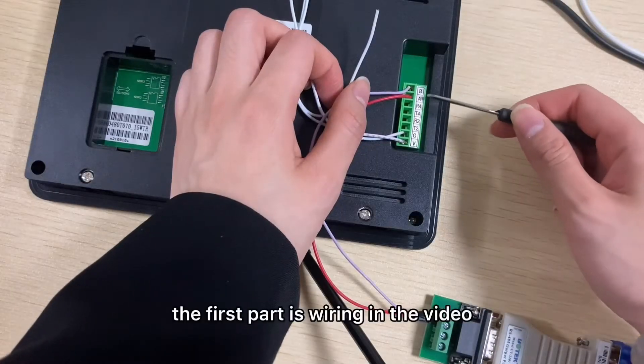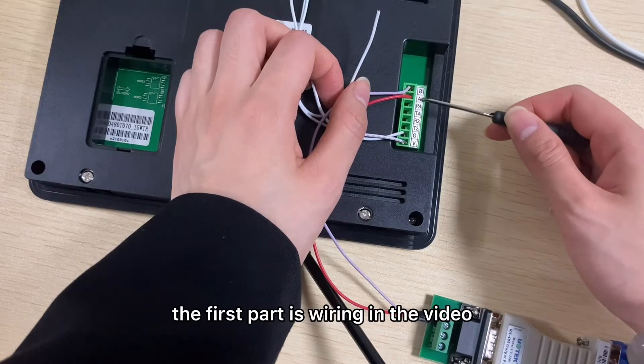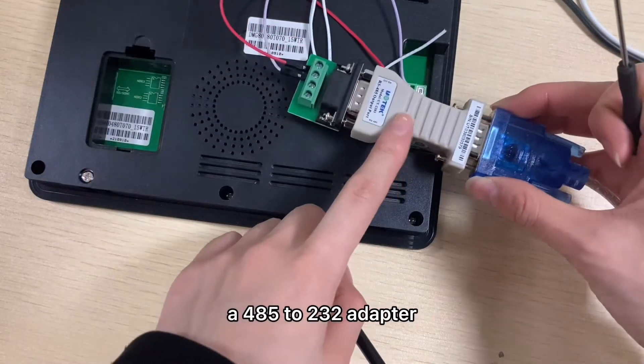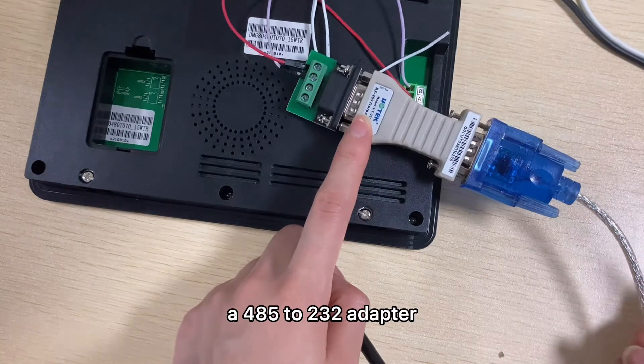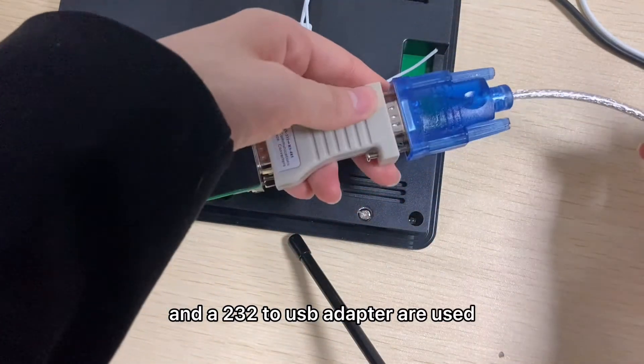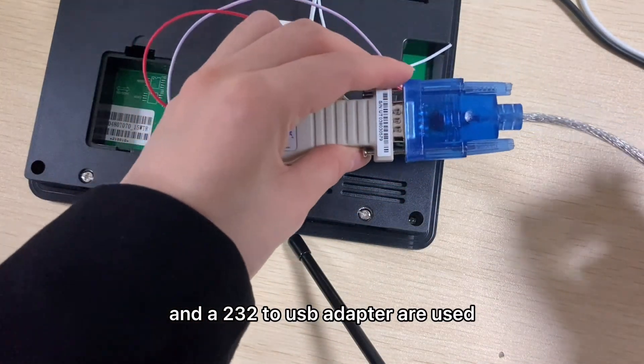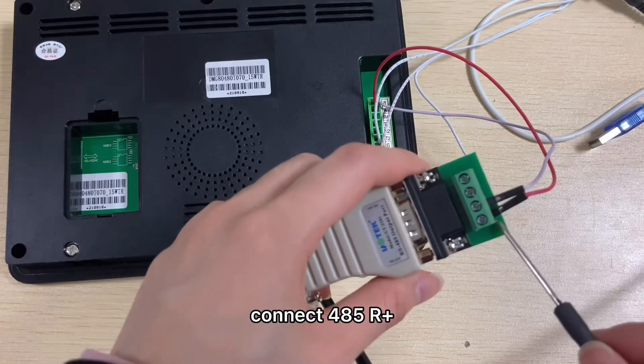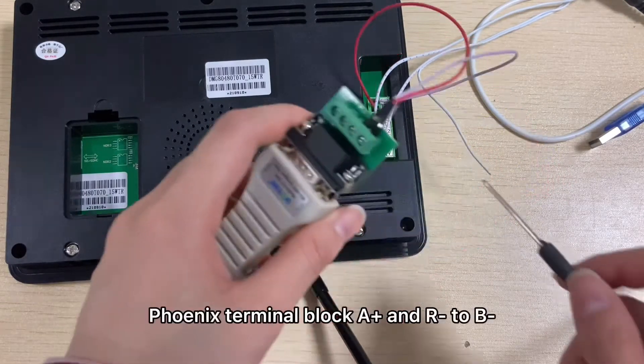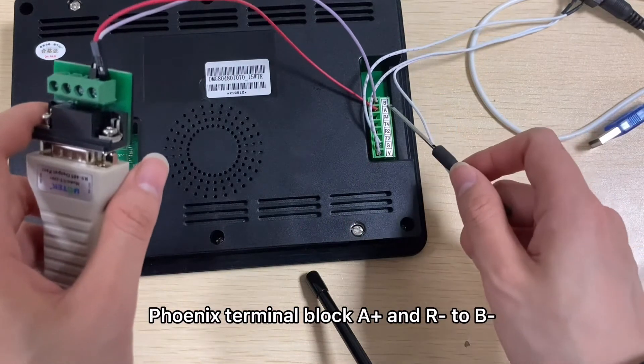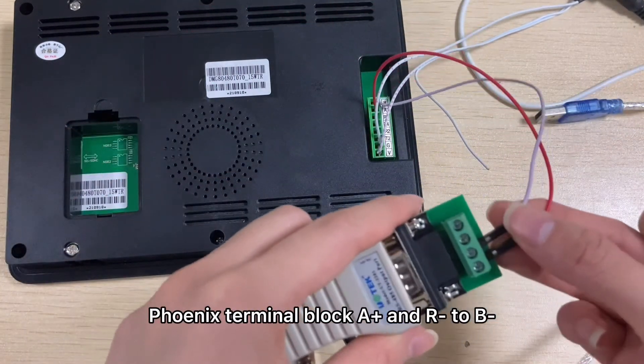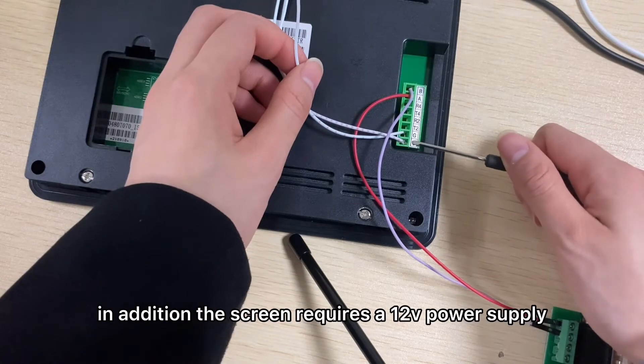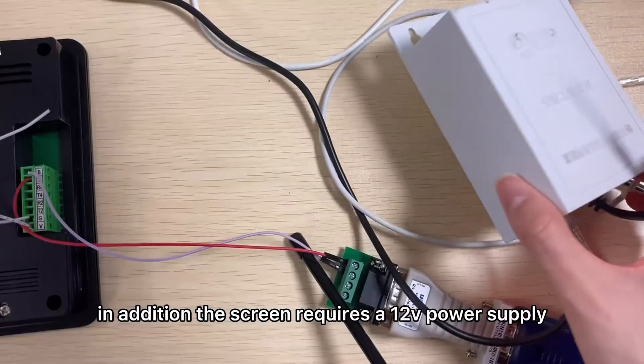The first part is wiring. In the video, a 485-232 adapter and a 232-USB adapter are used. Connect 485 R plus to the screen phoenix terminal block A plus, R minus to B minus. In addition, the screen requires a 12 volt power supply.